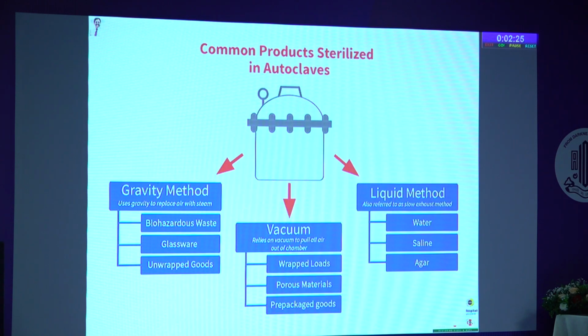Now, glassware and unwrapped goods. This is what we are using in camps or in yesteryears when there were only small instruments. Now we have the vacuum-based autoclaves. This is basically very good for wrapped loads and porous materials as well as tubings and cannulas. So basically we have to package the goods for sterilization. Of course, liquids we are not sterilizing, but some of them want to sterilize everything like BSS or Visco. In those cases, this autoclave for water, saline and agar and a few chemical consumables would be useful.